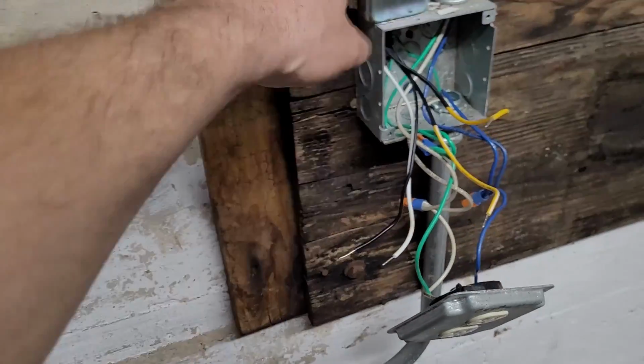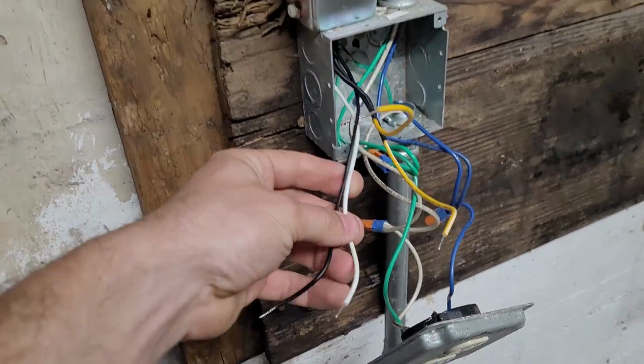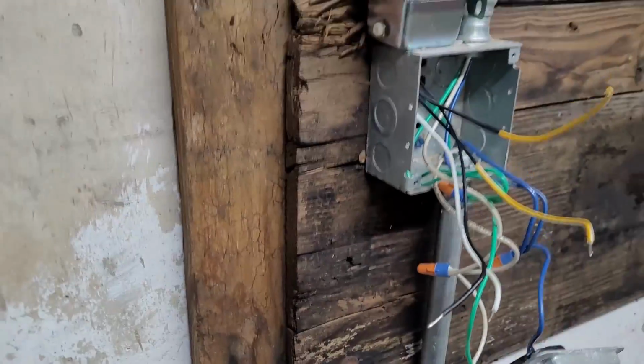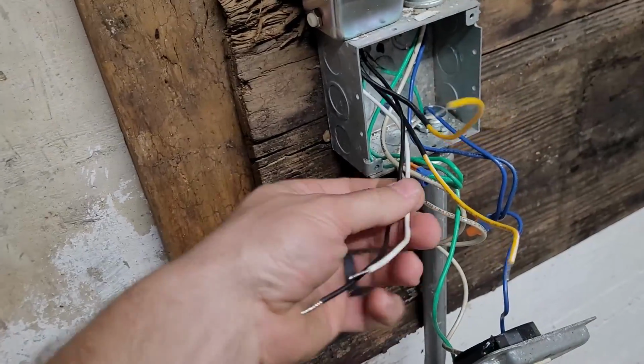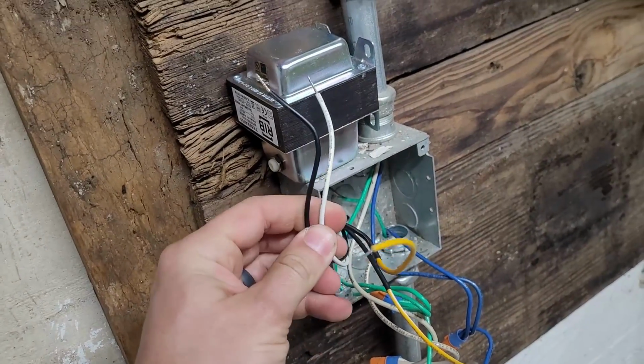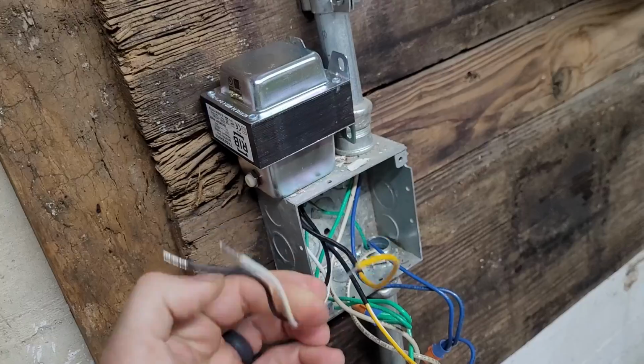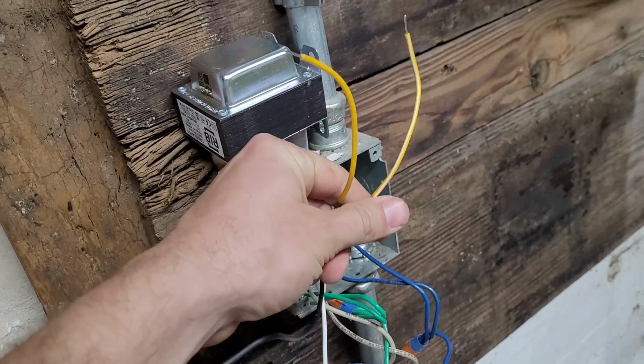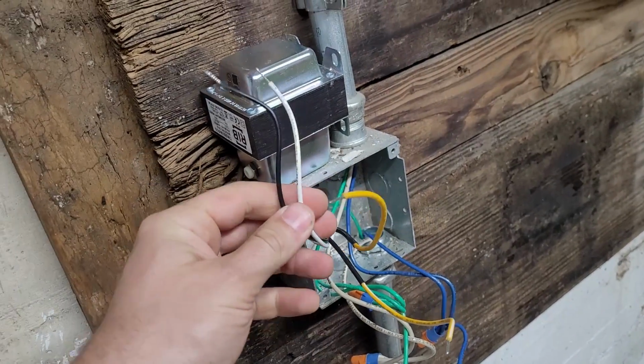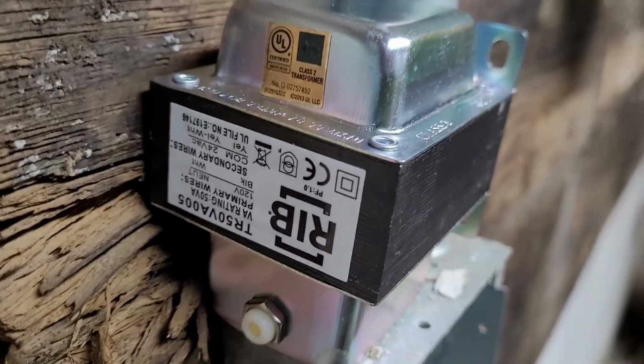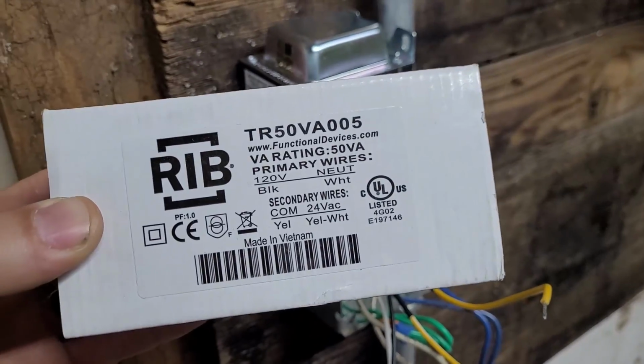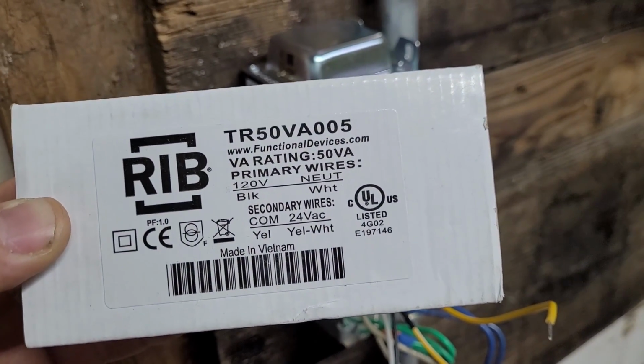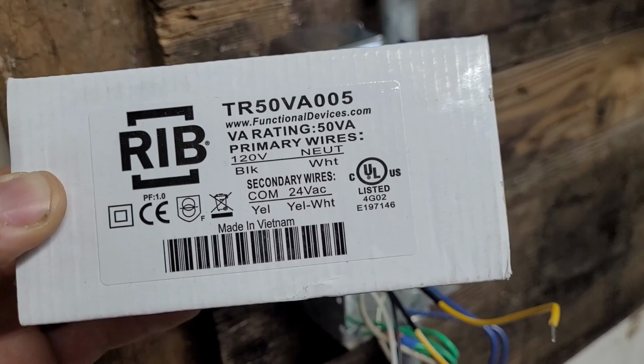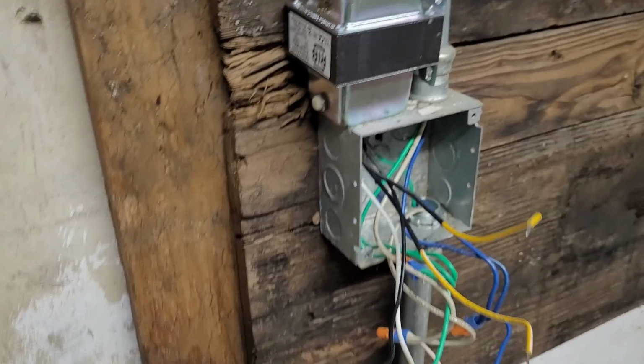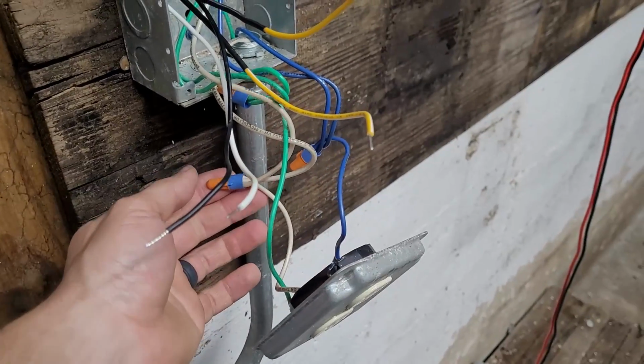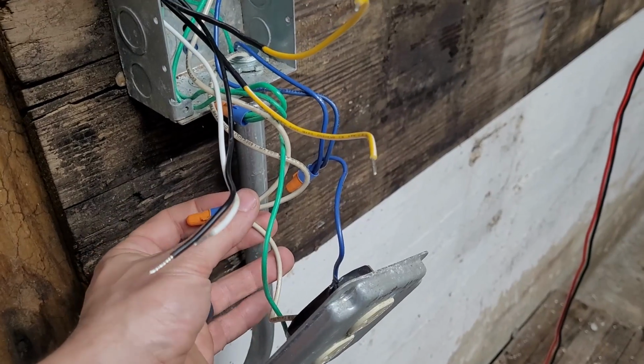So it goes right in the knockout, and then you need to look at your primary colors and your secondary colors. You've got a line side, which is going to be the 120 volt, and then you've got the load side, which will be the 24 volt, or high side and low side. So it'll tell you right on there what you've got, and this one says black is the 120 and white is the neutral, and then the secondary is the yellow and yellow-white. So with 120 volt on a receptacle, it really ought to be white for neutral.